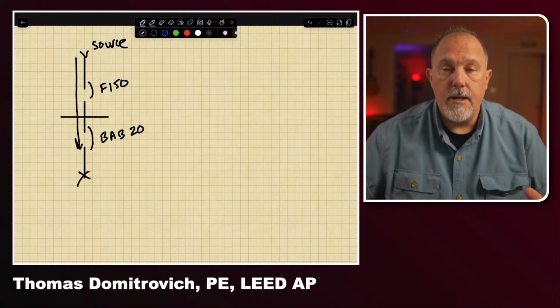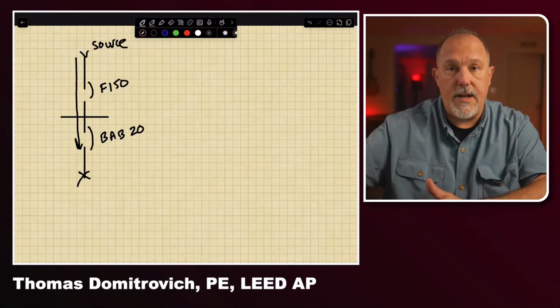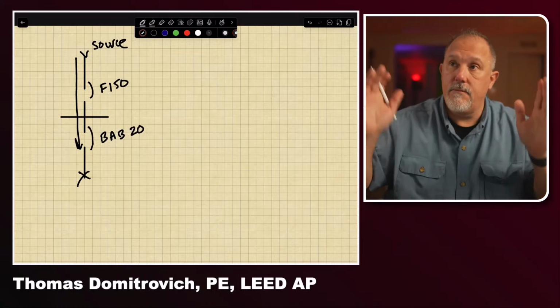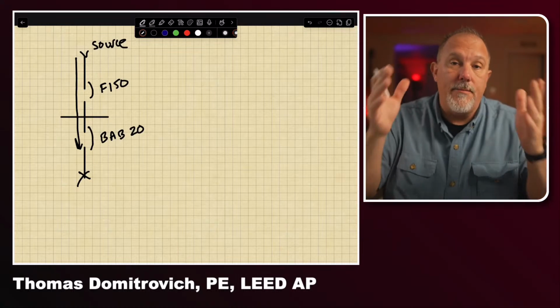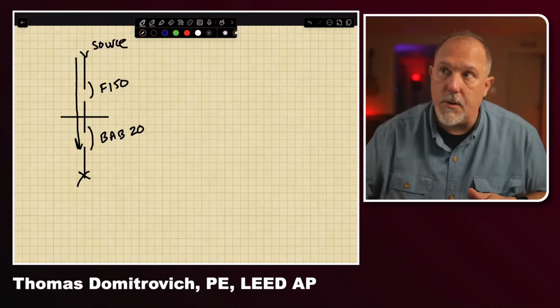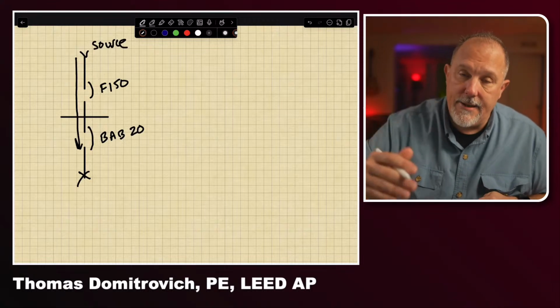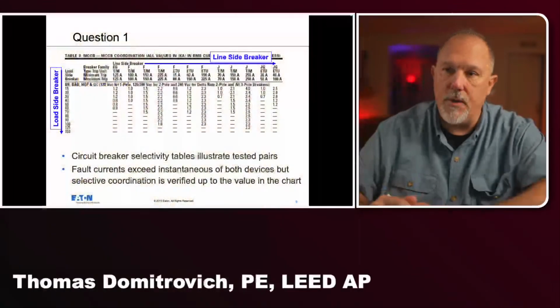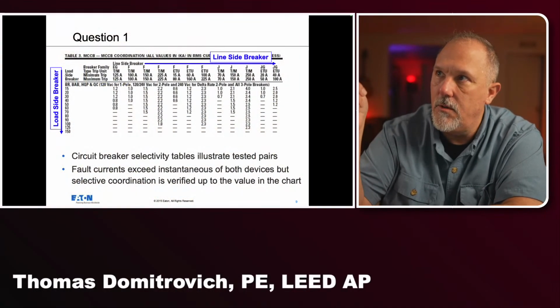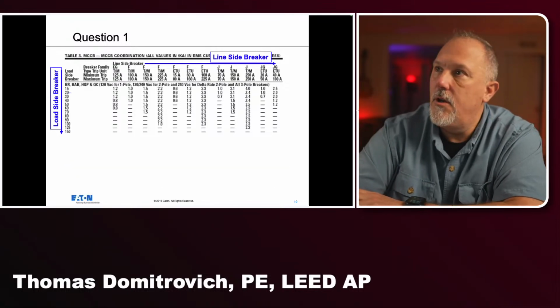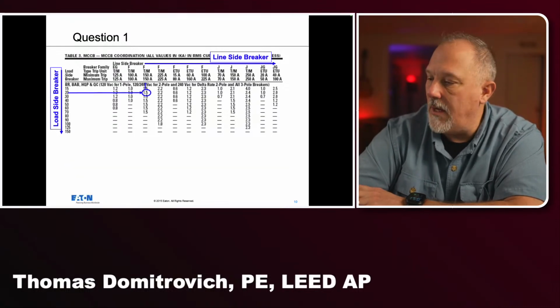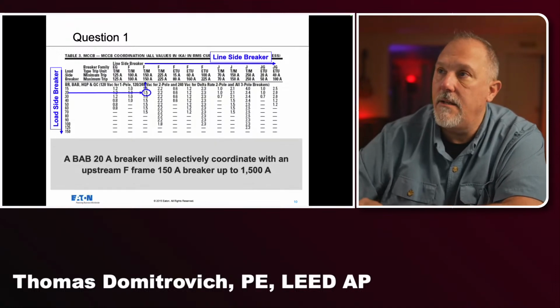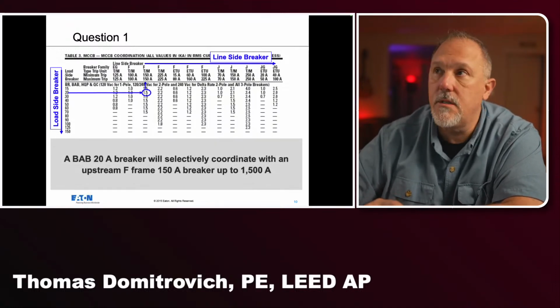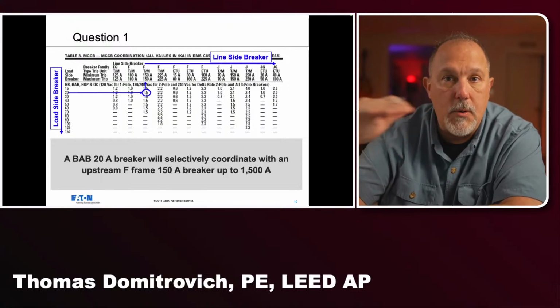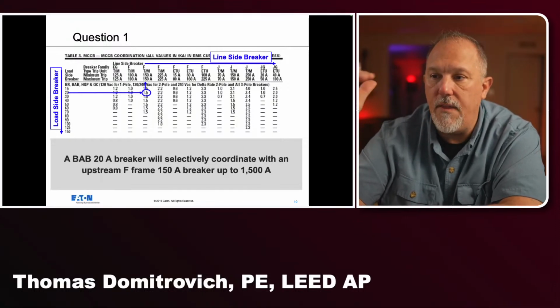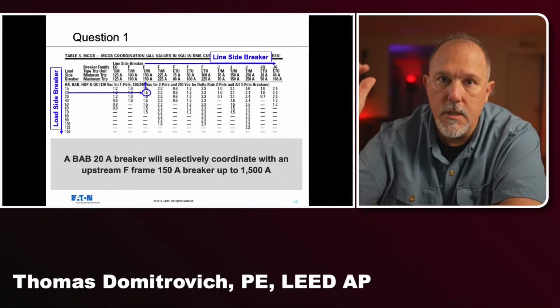trip. Now, once we know the fault current value, I'm in a lab, so I'm driving current through both of these circuit breakers. When I hit that number and I know they both open, we plot that in this table. So we know that for a BAB20 downstream of an F150, 1500 amps is where that point is, that line of demarcation, when they both open.